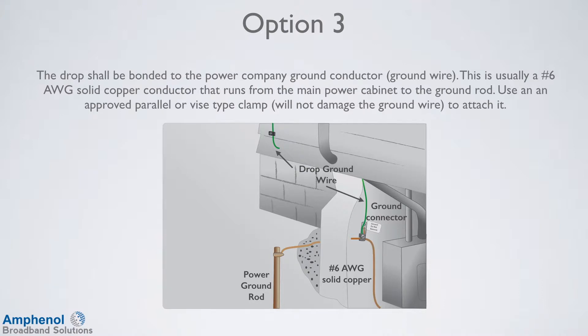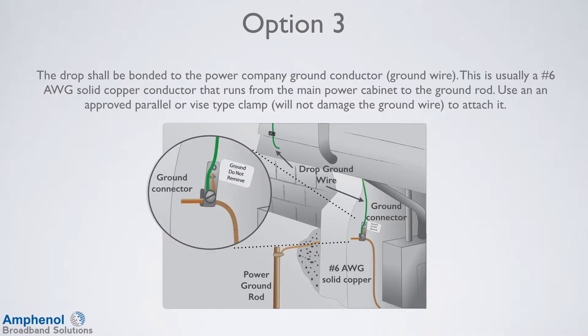In option number 3, the drop is bonded to the power company ground conductor or ground wire. This is usually a number 6 gauge copper wire or conductor that runs from the main power panel to the ground rod. Use an approved parallel or vice type clamp that will not damage the ground wire to attach it. Make sure the contact point is free of corrosion. Also visually ensure that the wire you are attaching to actually makes contact with the ground rod or grounding electrode.